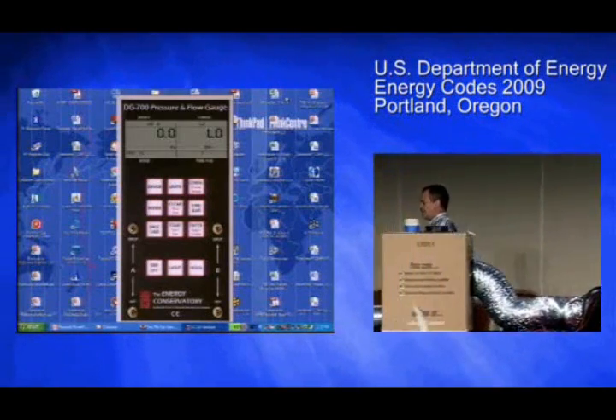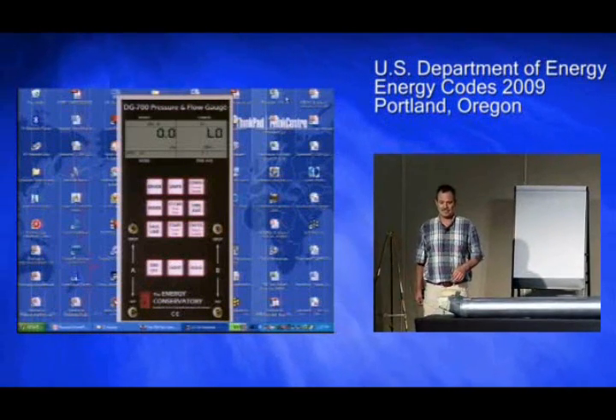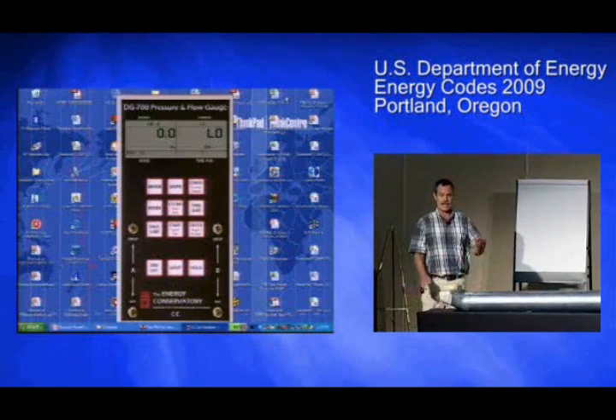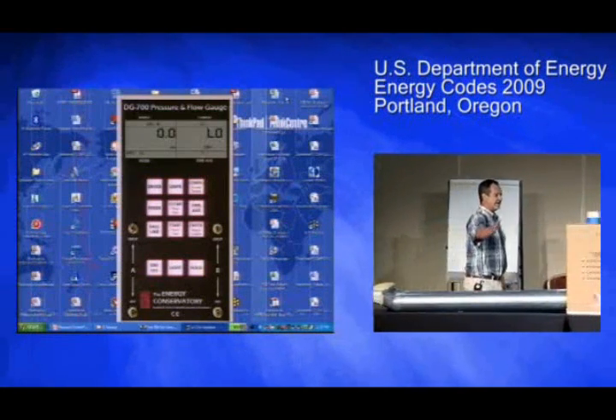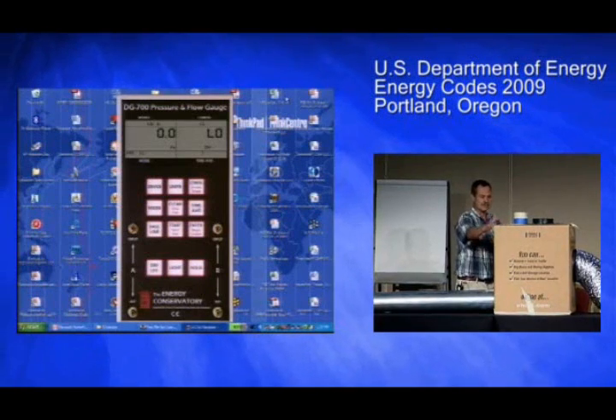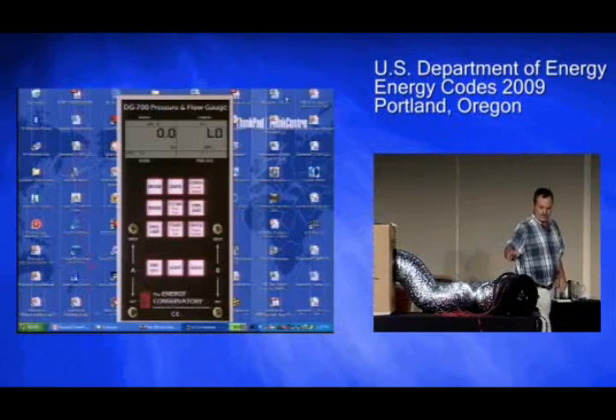What we've done here is we have two registers in the whole house because we got kind of stretched on the HVAC budget. We've taped one off, and this is the one our pressure tap is in. I used a foam block on this one. This is supposed to be our U-Haul air handler box — it's green, it's a recyclable furnace — and this is lovingly called the snorkel, and it fits to the fan.